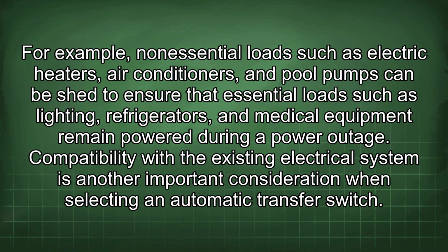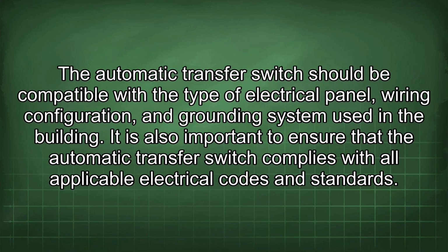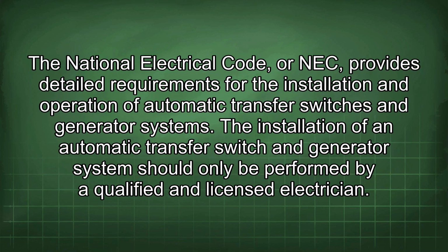Compatibility with the existing electrical system is another important consideration when selecting an automatic transfer switch. The automatic transfer switch should be compatible with the type of electrical panel, wiring configuration, and grounding system used in a building. It is also important to ensure that the automatic transfer switch complies with all applicable electrical codes and standards. The National Electrical Code, or NEC, provides detailed requirements for the installation and operation of automatic transfer switches and generator systems.